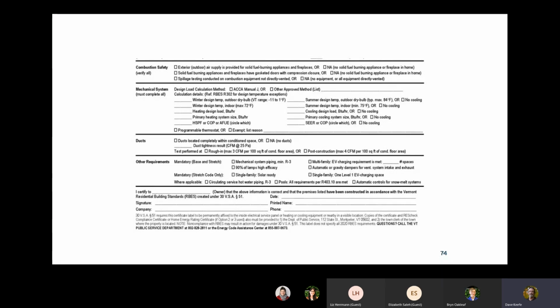I should be more specific. If your heating system person tells you that they haven't done a Manual J, you should inform that person that it's required by law, and it's their requirement to do it, and it's their requirement to give you those numbers. And then you also fill in your primary heating system size and your primary cooling system size. So you're going to be filling in the heating design load and the output of your heating system. And you remember the heating system output has to be no more than, depending on the type of system, either 15% or 40% higher than the design load. So it's going to be very obvious right here whether you've met that requirement or not.